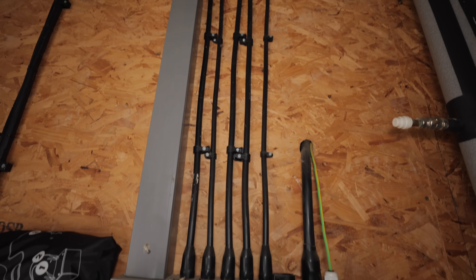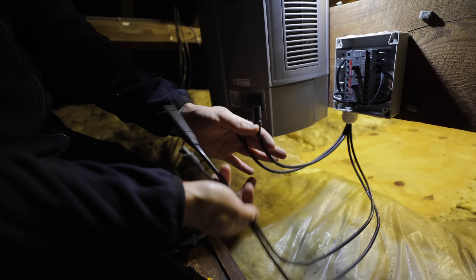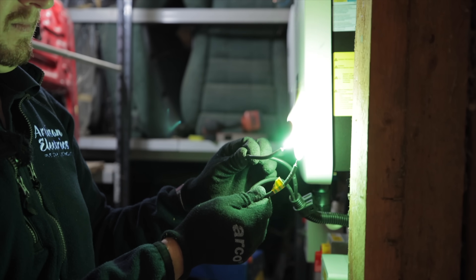When it comes to electrical safety, that's a whole other can of worms. DC power from the roof, including the voltages from the solar panel cables, can be quite dangerous. DC doesn't pass through zero like AC, so if you get a DC shock you can't let go — it's very dangerous. DC arcing can also easily cause fires because the arc just keeps going until something catches fire and forces the wires to separate. So from a fire safety and electrical safety point of view, there are so many risks with poorly installed solar systems.